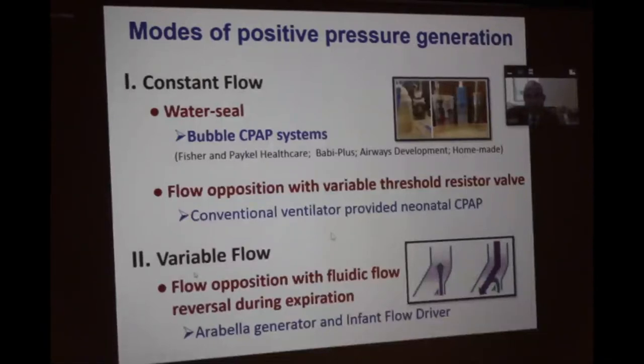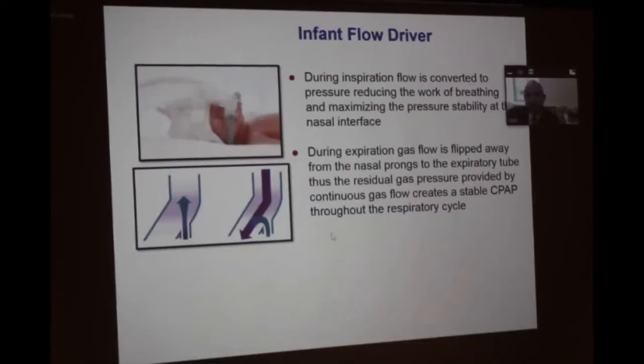In contrast, the variable flow system has flow opposition with fluidic flow reversal during inspiration and expiration, where gas is entrained during inspiration to maintain stable pressures. During expiration, the expiratory flow is diverted via a separate fluidic flip-flop valve. The Arabella generator and the infant flow driver are typical examples of this system.